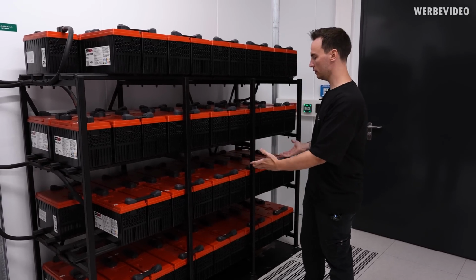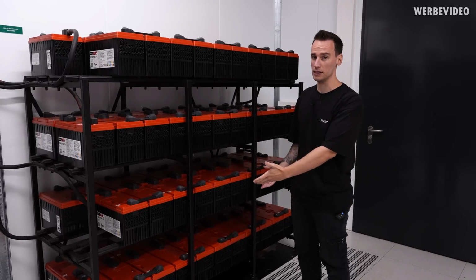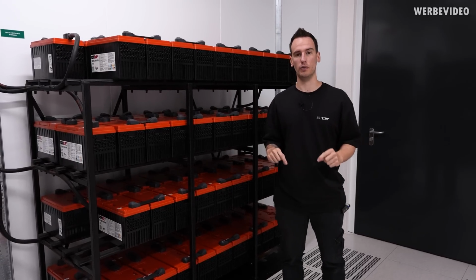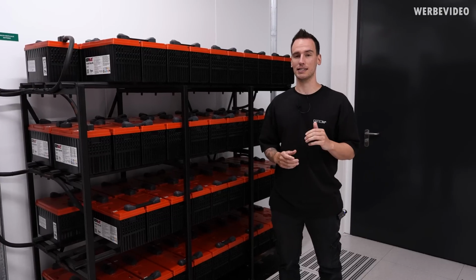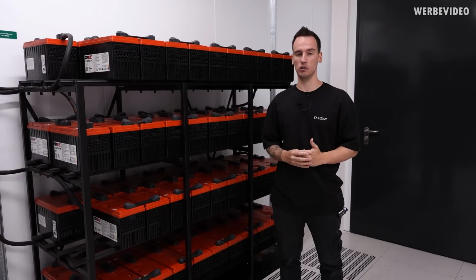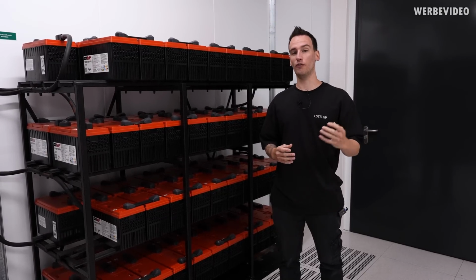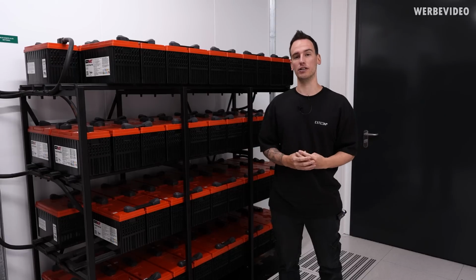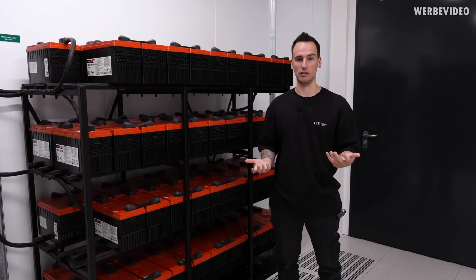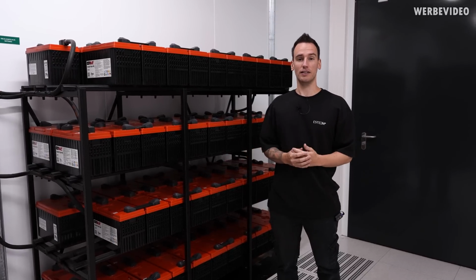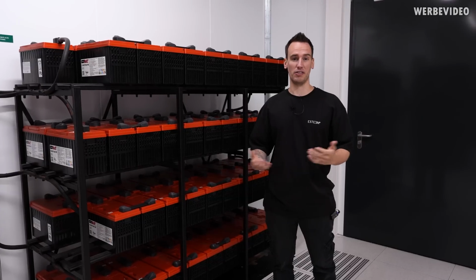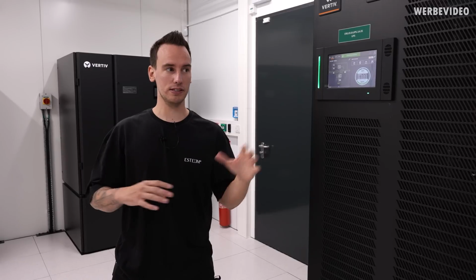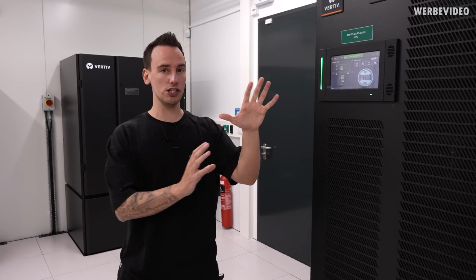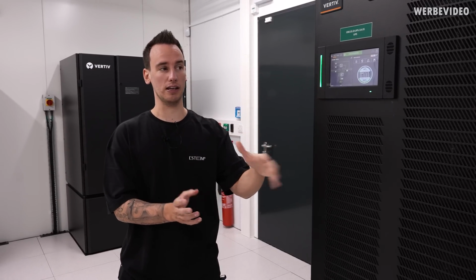This isn't a huge amount of batteries next to me, because this room where we're standing and filming is one of 8 UPS rooms. Only 4 of them are technically required to keep the data center running, so technically 4 of them could fail and nothing would be a problem. In this current setup, the energy is always flowing through the batteries, all the time.